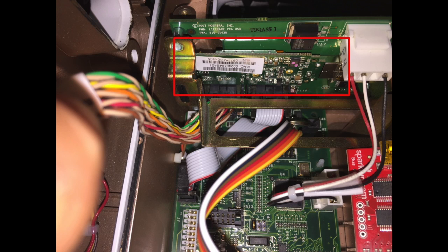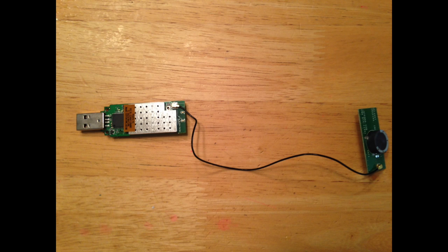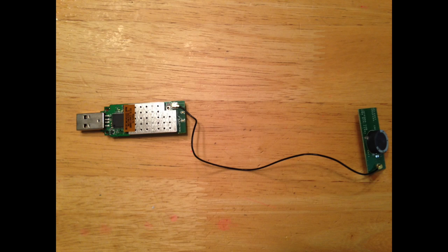If you look really closely, there's also JTAG and debug and an RS-232 port that's identified in the architecture as well. So if we look at the communications board, this one's from a little bit of an older version. We actually see that the communications is actually really handled by a USB Wi-Fi adapter, right? And so that can tell us a couple different things. What I infer from that is that the Wi-Fi connectivity is actually bolted on, right? It's not something that was designed in this pump from the ground up. So this was definitely bolted on. That sticker tells us the MAC address and a serial number for the particular Wi-Fi adapter, which could be useful if we're trying to find this on the internet or within a network. So pretty interesting stuff here.